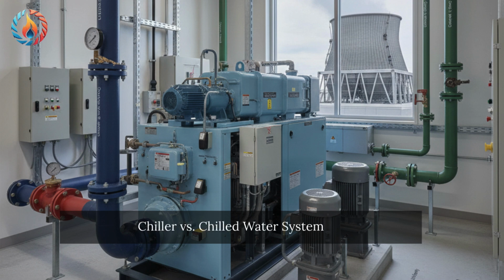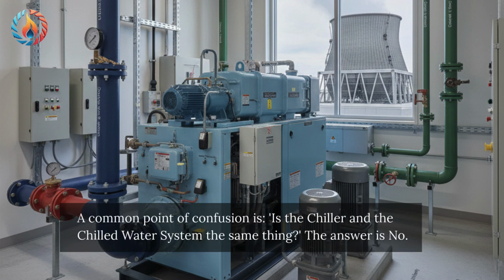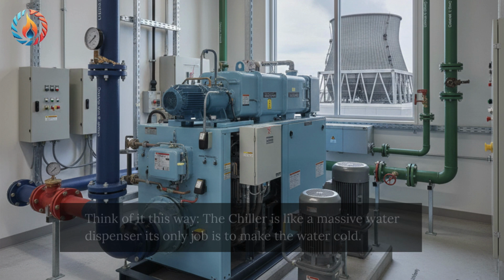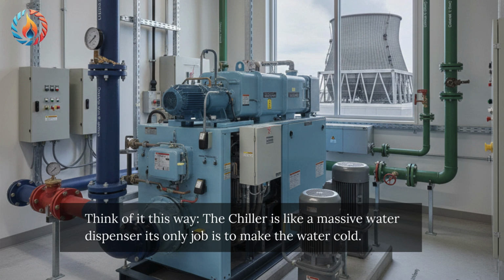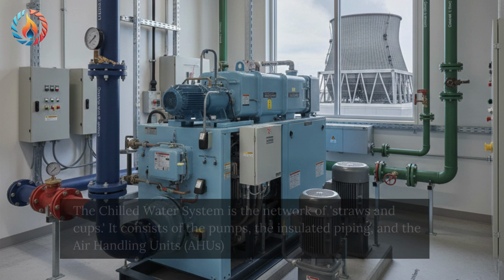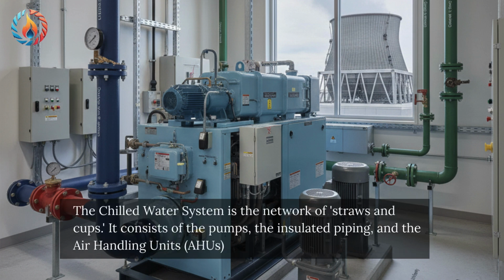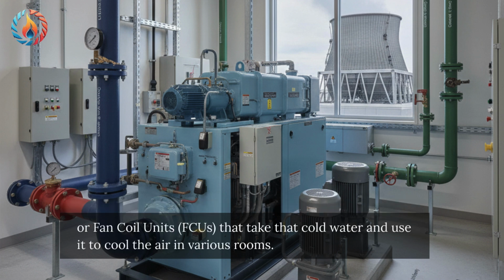Chiller versus chilled water system. A common point of confusion: are the chiller and the chilled water system the same thing? The answer is no. Think of it this way. The chiller is like a massive water dispenser. Its only job is to make the water cold. The chilled water system is the network of straws and cups. It consists of the pumps, the insulated piping, and the air handling units (AHUs) or fan coil units (FCUs) that take that cold water and use it to cool the air in various rooms.